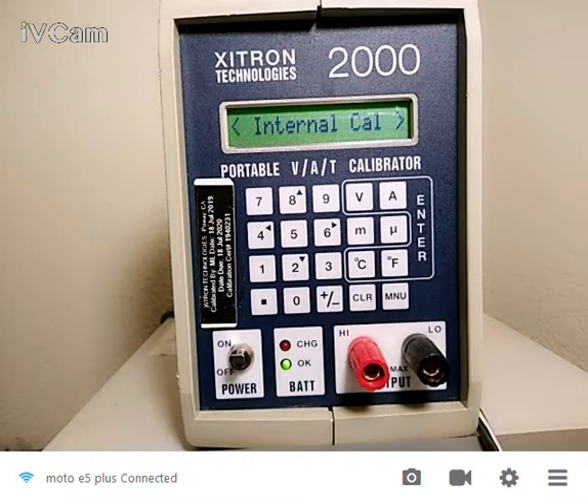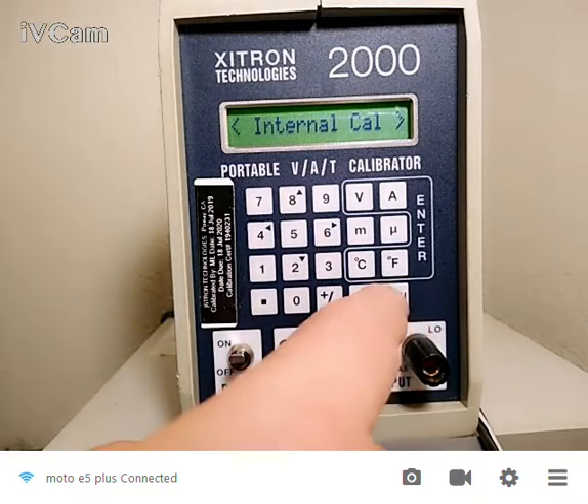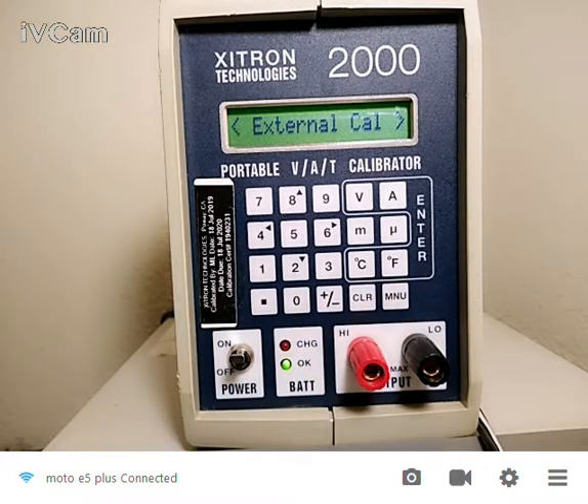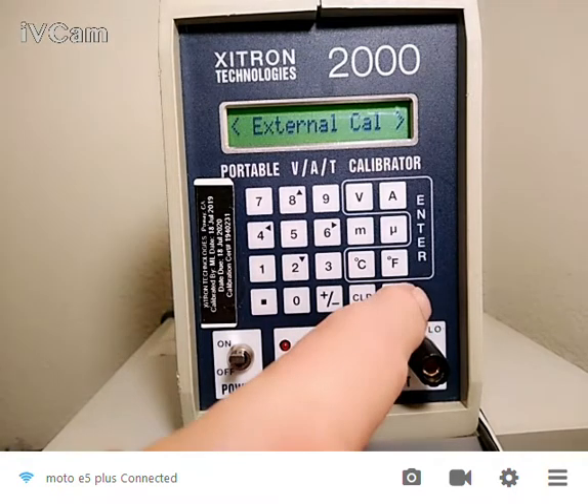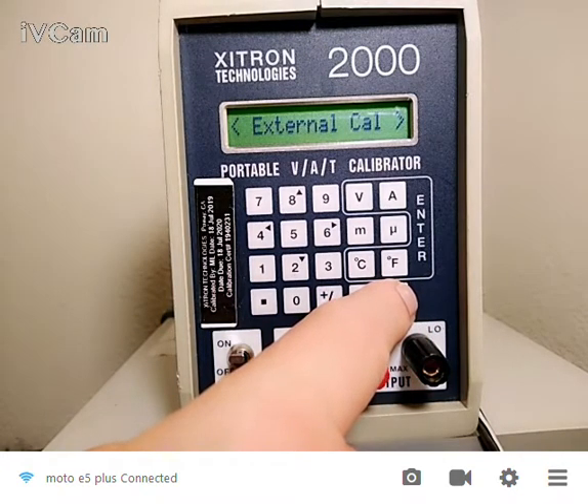Internal cal: it has its own internal cal standards, and if I hit enter, it will go in and do a calibration to its own internal standards. That takes about 2 minutes. The next choice is external cal, so obviously you want to have this calibrated externally. You put up the external standards to it. There is a 90-day spec and a 1-year spec for this instrument. So for the very best performance, we recommend calibrating this every 90 days. But if you don't need the very top performance, then you can extend that out to 1 year.